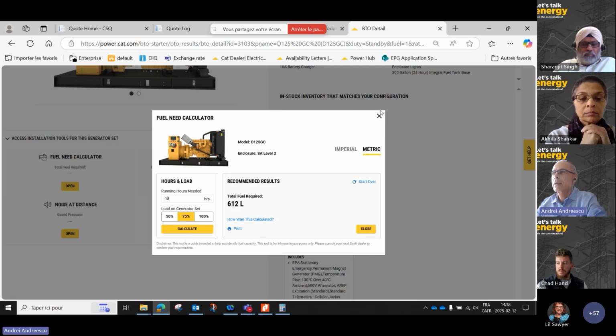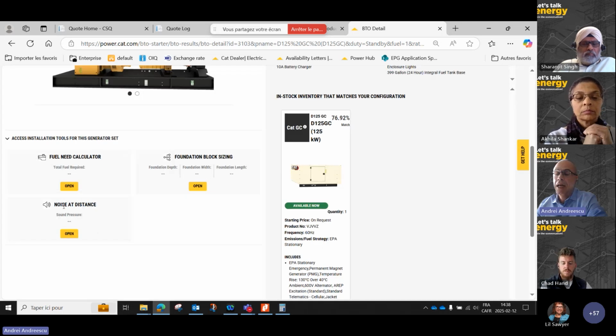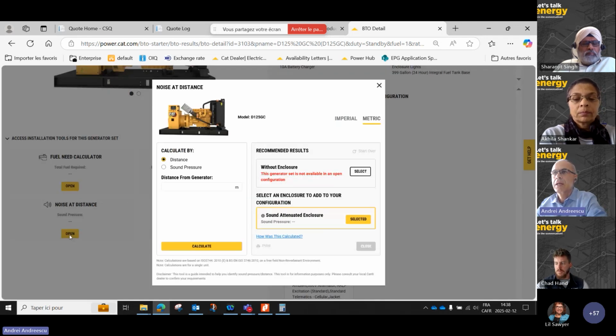There is another interesting tool that calculates the noise level. This is important when deciding where to install the generator - do you have neighbors who could complain about the noise? The tool can be used in two ways. You can input the distance - we've seen that the enclosure offers a noise level of 75 dBA at 7 meters.